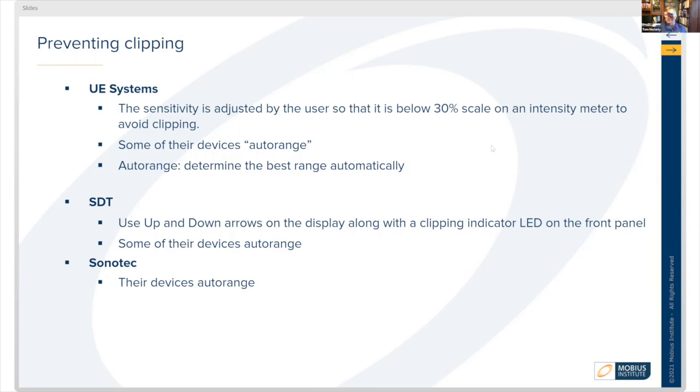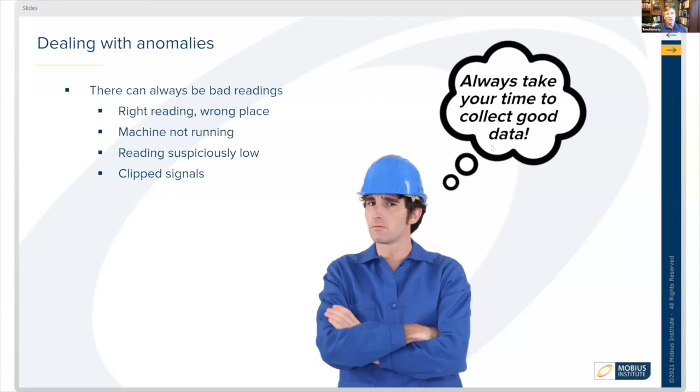With Sonotec, all devices auto-range. There can be anomalies—bad readings can occur. You could take the right reading from the wrong place, collect data on a machine that's not running, or get suspiciously low or clipped signals. Always take your time to ensure you're collecting good data.